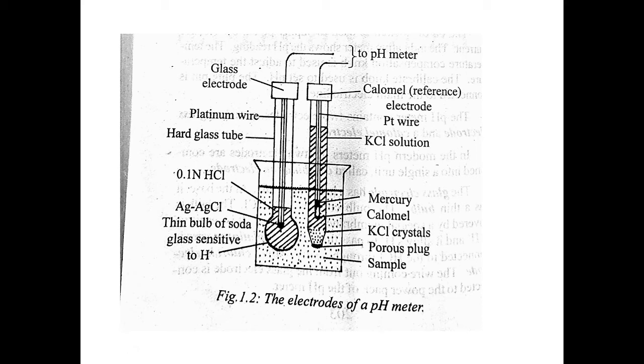Modern day pH meters do not have two electrodes. They use a single electrode, which is called a combination electrode. And the glass electrode, when they used two electrodes, one was glass and it consists of a platinum wire connected to the HCl solution through a silver chloride electrode. Then another was the calomel electrode, which is called the reference electrode. This calomel or reference electrode is not sensitive to hydrogen ion. It contains calomel, that means mercurous chloride, and hence the name. The calomel is connected to a platinum wire through mercury.